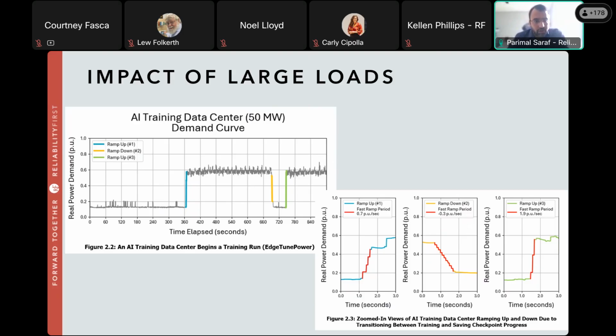So if you look at the snapshot on the right, the ramp up on the leftmost picture is from 0.15 per unit on a 50 megawatt base, which is around 7.5 megawatts, to around 0.6 per unit, which is around 30 megawatts. So this power ramp up goes from 7.5 megawatts to 30 megawatts in a matter of a few seconds, less than 2 seconds essentially. So this is a 50 megawatt data center. Imagine if it was a 500 megawatt data center, imagine the spike, or this ramp up profile, that the grid would have seen.